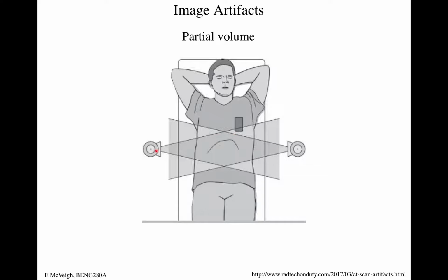However, when this thing's rotating around, you can see that in this view, these slices or these rows of the detector are seeing this tissue here. And then when it rotates around 180 degrees, they're missed, right? And so you basically can adequately reconstruct a kind of football-shaped thing, as opposed to a cylindrical volume, right? So that's taken into account when you calculate what is my field of view in this direction.